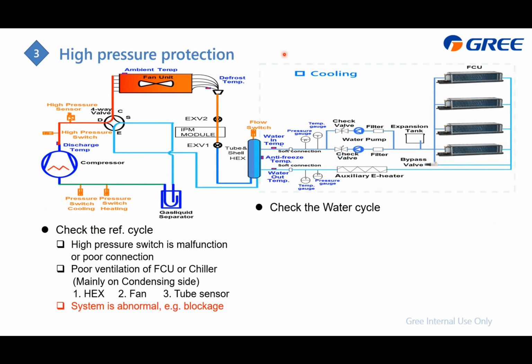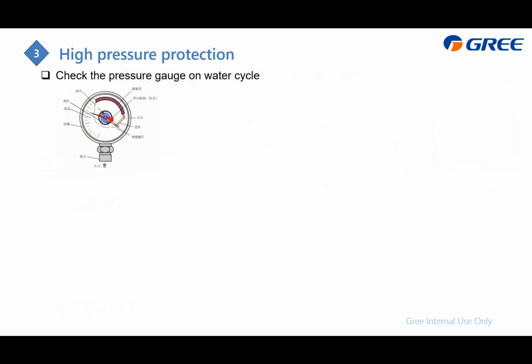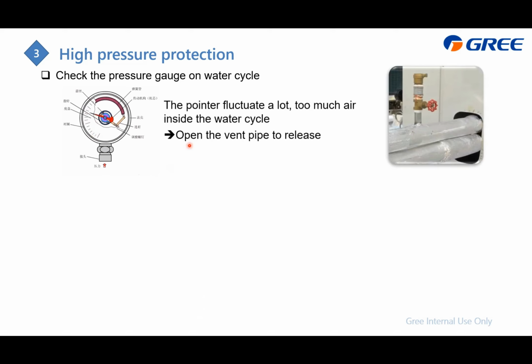And let's go back to this slide, and after 15 minutes, just focus on the water cycle. So for the water cycle, first is to check the pressure gauge. If it looks like this, which means you can see the pointer just vibrates a lot, that means too much air is trapped in the water system. So you can just open this vent pipe to release it. It's okay.